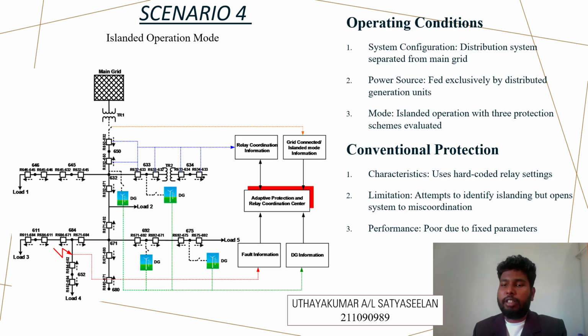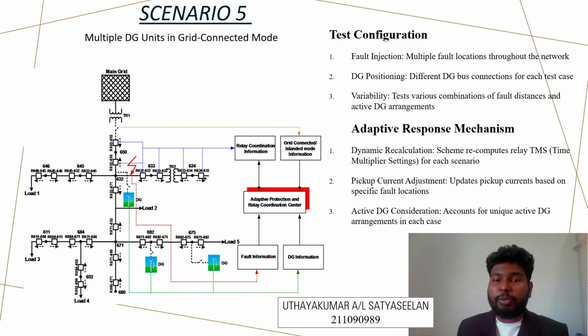And for the operating condition, the islanded operation mode system, it separates from the main grid, which is more secure. And also for the conventional protection, uses hard-coded relay settings. The limitation here is it attempts to identify islanding, but open system oftentimes will cause miscoordination. So there's some limitation in terms of conventional protection compared to the operating condition, which is used in islanding operating mode. And the last one, which is the multiple DG units connected.